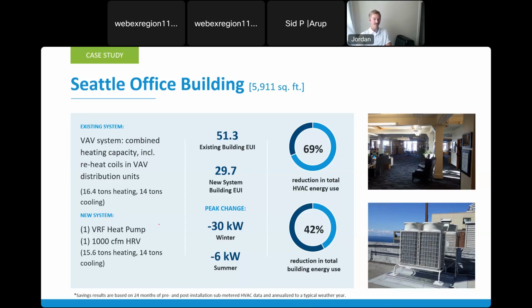The system did that with a 14-ton VRF system and 1,000 CFM HRV. Another big result that utilities care a lot about, and I think building owners should care about too, because it's going to start being a significant part of their energy bill, is demand costs. The change in peak winter demand was a 30 kW reduction. So in the coldest 15 minutes of the month, the conversion system used 30 kW less. That's pretty significant for this little 6,000 square feet of office space. Likewise, about a 6 kW reduction in peak summer demand.